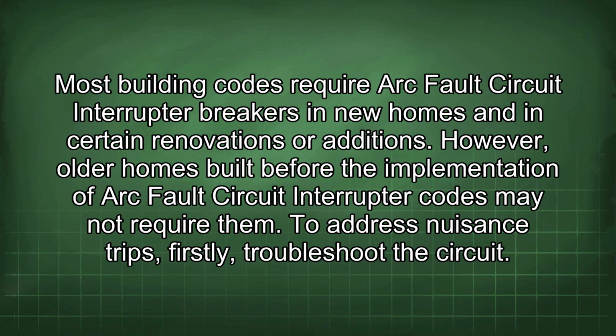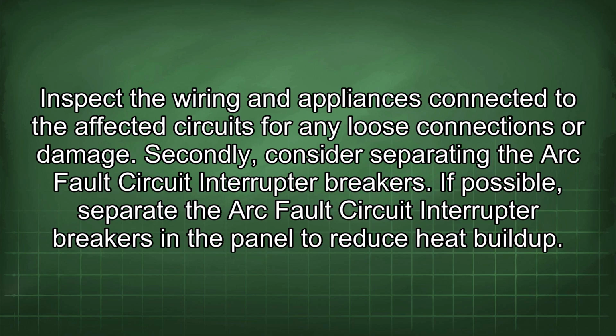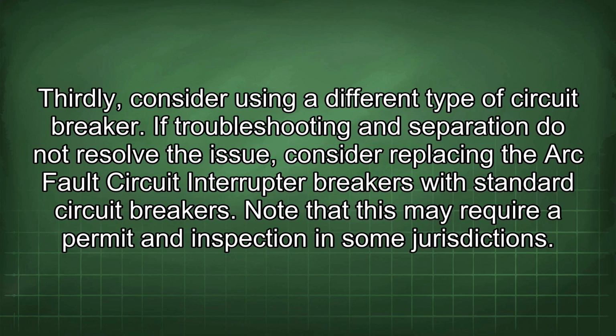To address nuisance trips, firstly, troubleshoot the circuit. Inspect the wiring and appliances connected to the affected circuits for any loose connections or damage. Secondly, consider separating the arc fault circuit interrupter breakers. If possible, separate the arc fault circuit interrupter breakers in the panel to reduce heat buildup. Thirdly, consider using a different type of circuit breaker. If troubleshooting and separation do not resolve the issue, consider replacing the arc fault circuit interrupter breakers with standard circuit breakers. Note that this may require a permit and inspection in some jurisdictions.